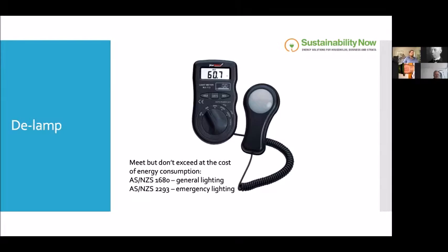The two standards to look at: Australian Standard 1680, for general lighting, has a big table telling you what certain areas of your building need to be lit at - you can measure this with a lux meter. For example, a general car park area needs 40 lux. If you're exceeding that, and you have fluoros in the car park, you might be able to remove a fluoro tube from a double fitting and save energy, but you've got to make sure you still maintain compliance.